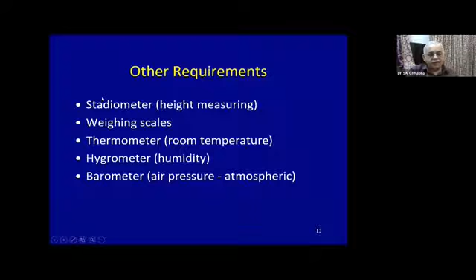Air expands on heating. If the ambient temperature is, let's say, 15 or 20, then the volume is smaller. But inside the body, it will be a little larger. So the temperature correction is applied. We have measured the volume at the ambient temperature in the room, and actually it is this much at 37. So whatever the temperature is in the room, that is recorded, and a temperature correction factor is generated. Humidity is required because we do the measurements at fully saturated air, and then atmospheric pressure is measured. So all these are entered in the first screen of the spirometer.